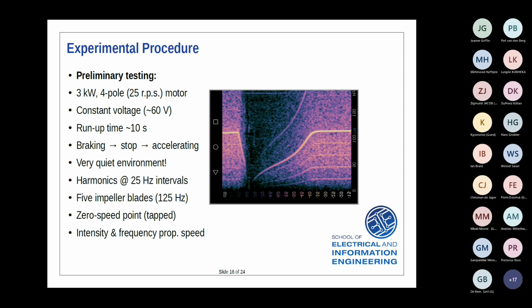Okay. And last comment here, intensity and frequency are proportional to speed. You can see the faster the machine is running, obviously the louder the sound. So it's very clear. I can hear exactly what speed it's running at when it's running at full speed. Obviously at lower speeds, it's a bit more difficult. So they're related to the speed.